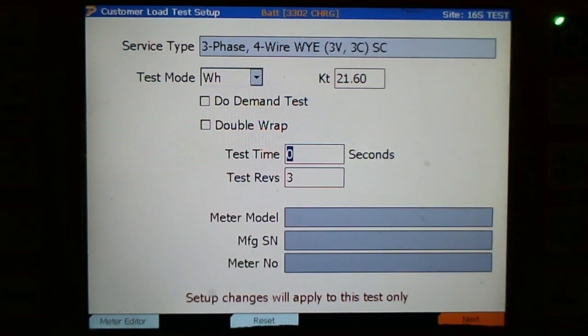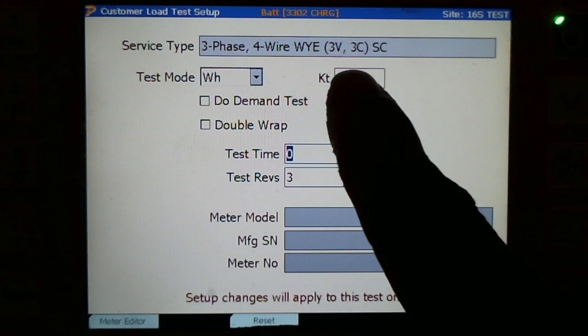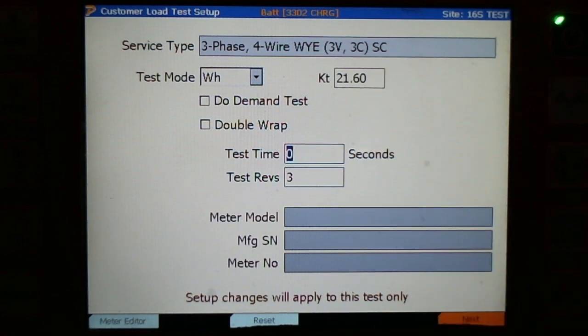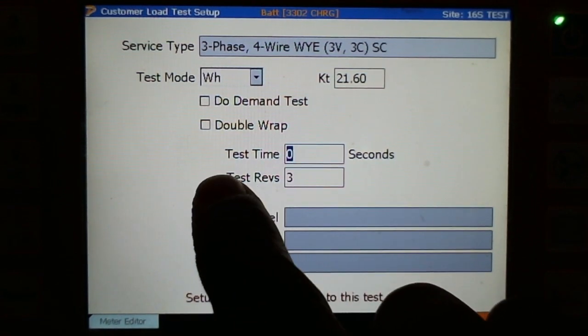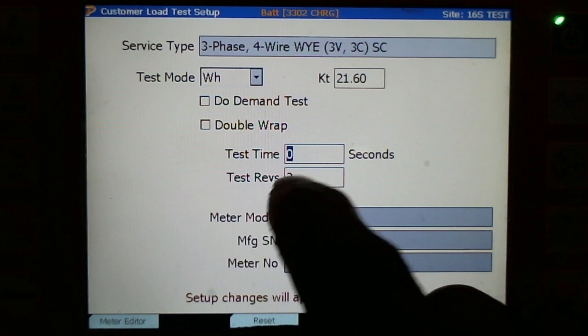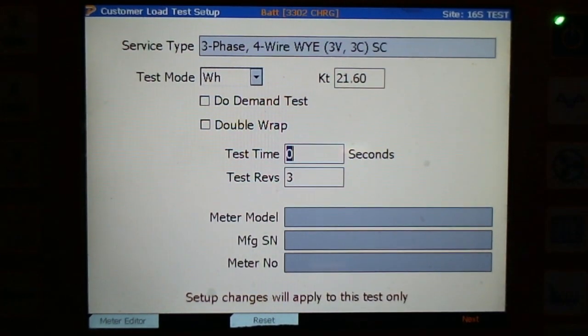So we verified the KT on the meter, which is 21.6 — I've already entered that. Test time is 0 seconds, test revs is 3. Everybody knows what 0 means: I'm looking for 3 revs and I'm not worried about time, so I'm watching my revs.